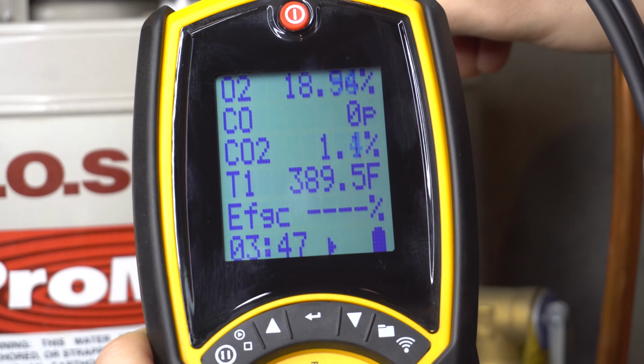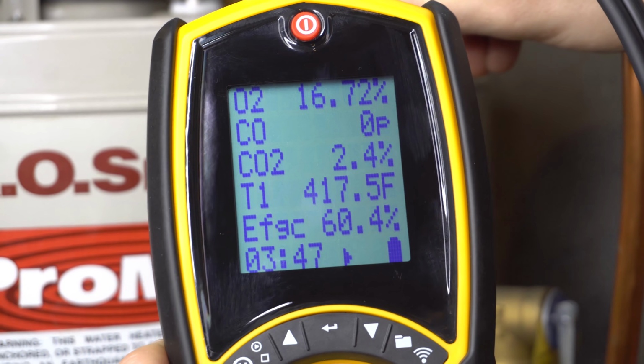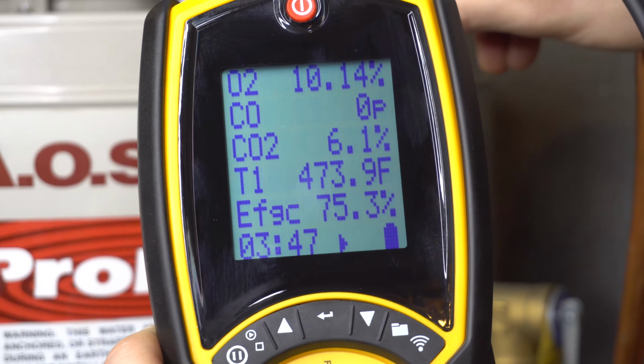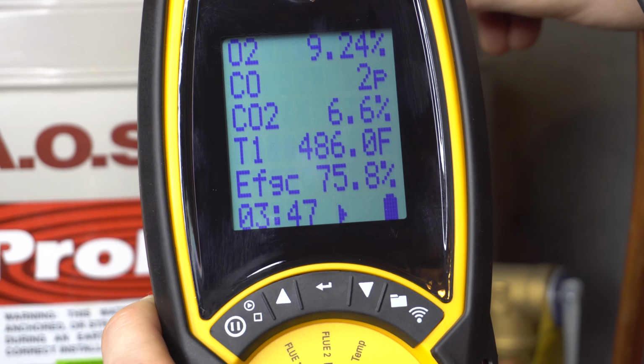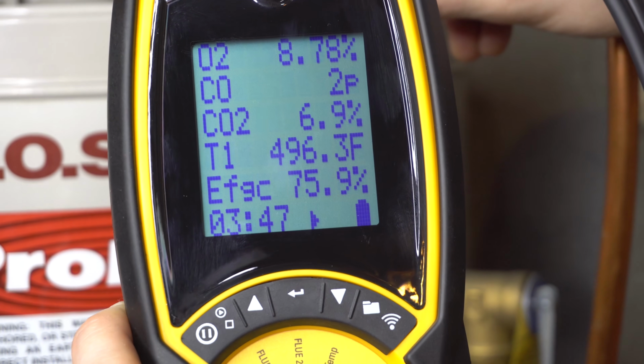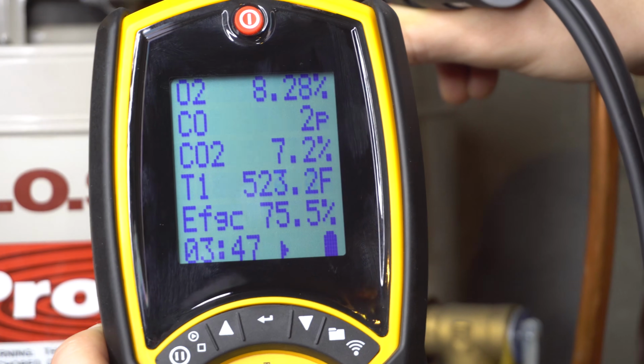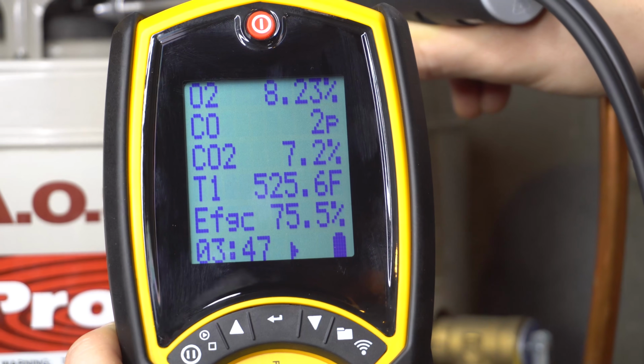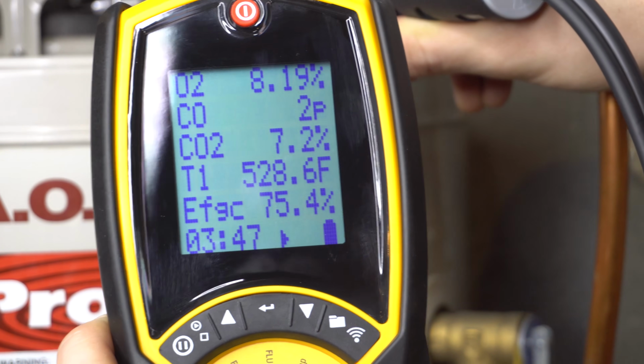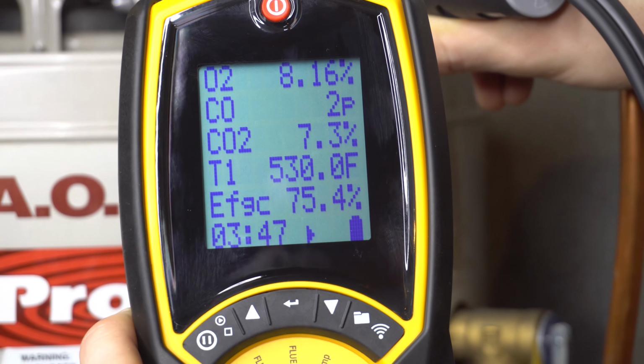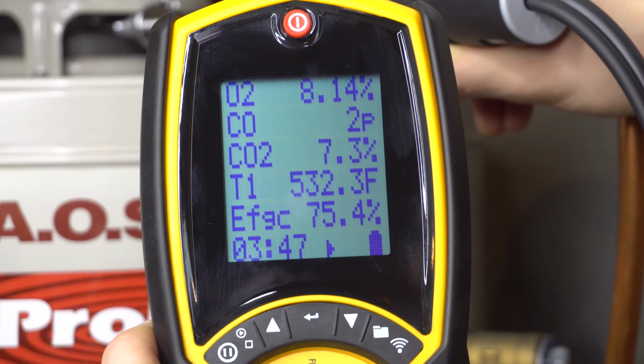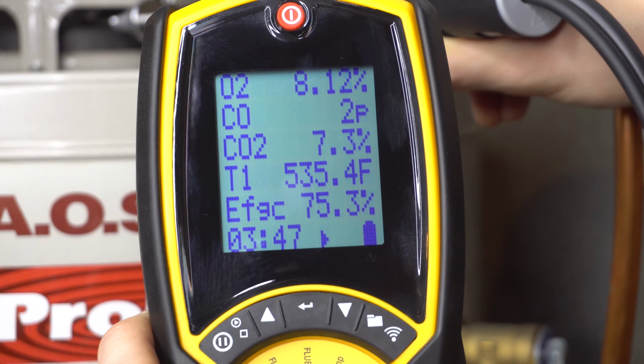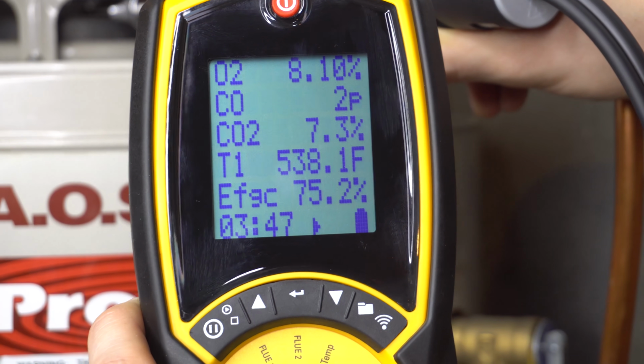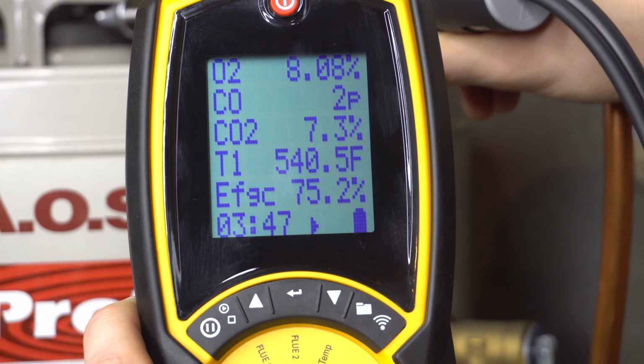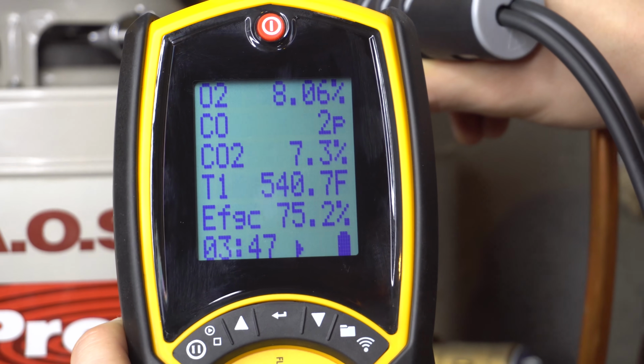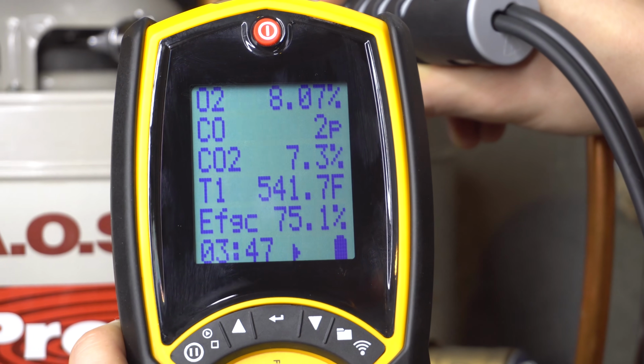There you go. My numbers are dropping. From what I've seen, water heater carbon monoxide emissions are generally very low. So I'm not surprised to see it at only 2 parts per million, which means it's burning really clean. For a water heater, it is kind of strange if you have parts per million going up to 300 or 400. That probably means that the burner is either really dirty or the intake screen on that water heater is really plugged up.